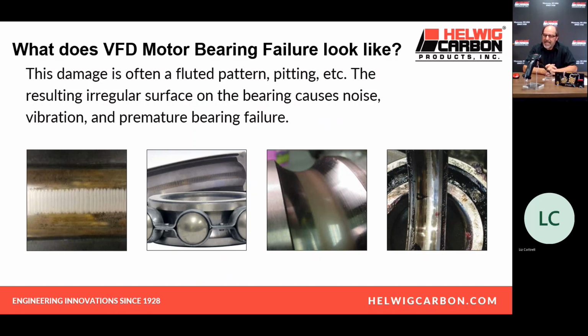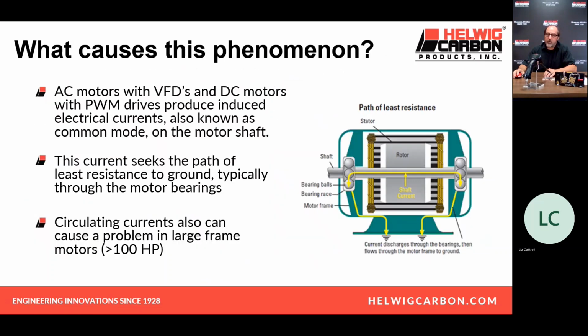You see that on the right? It's a leading indicator that the bearing has failed electrically. Okay, we're talking electrical failure, electromechanical, two different failure modes. Black grease, the fluting you see, and the frosted bearings are definite indications of electrical wear.